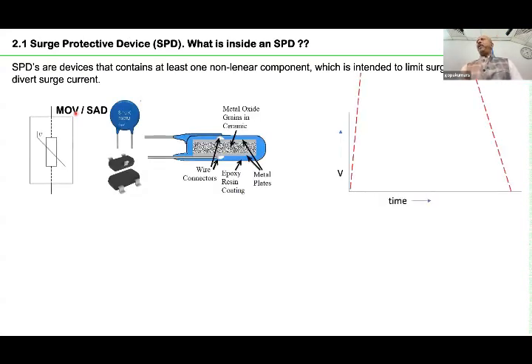Now, what is an SPD? SPD is a simple device. It contains some kind of non-linear device inside, for example, an MOV. You know very well that in an MOV, under normal condition, the resistance is very high. It is a voltage dependent device. Once the voltage is high, it changes its characteristics and the resistivity goes down to a very low level.